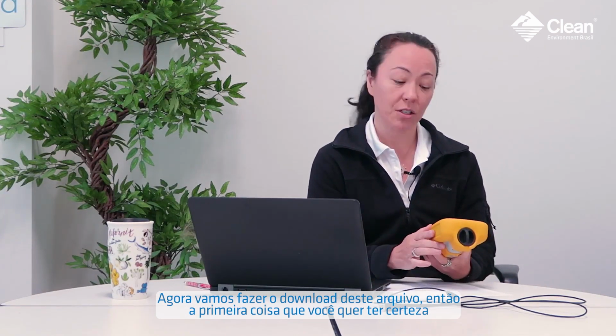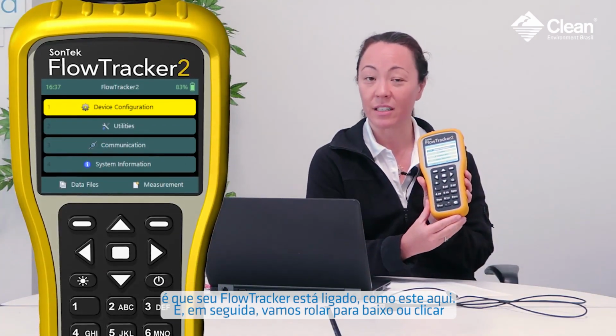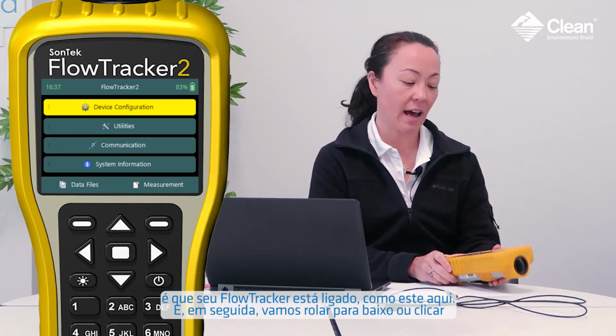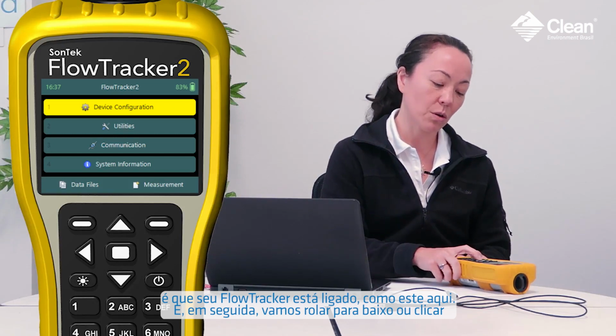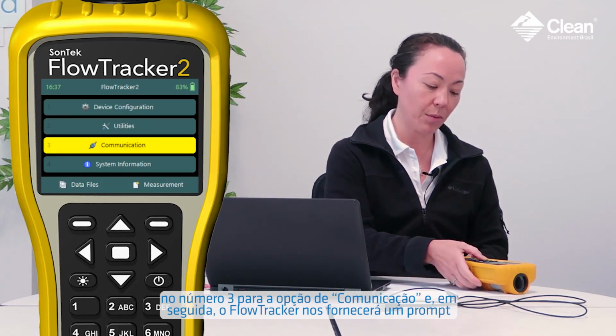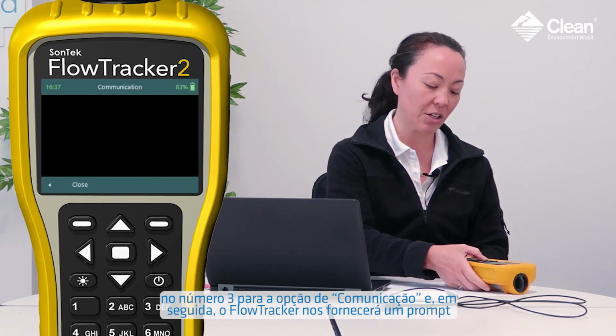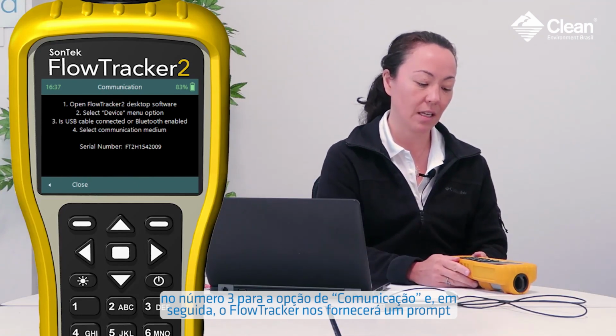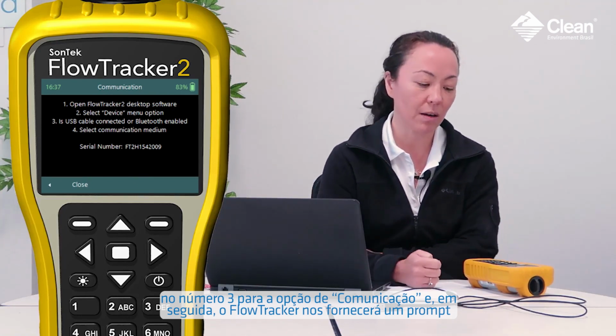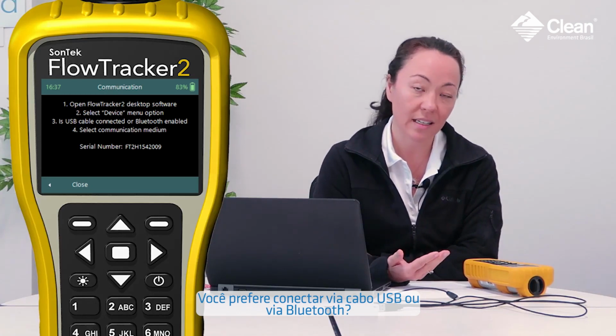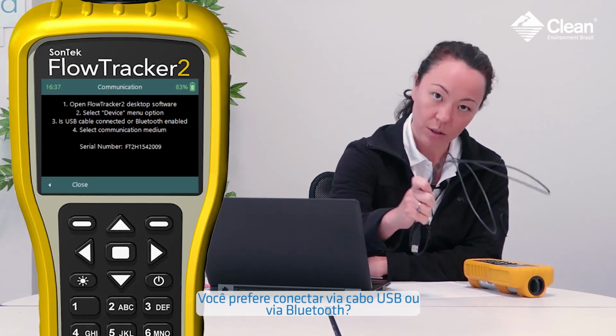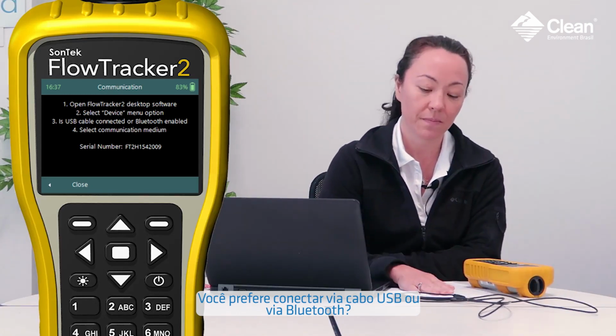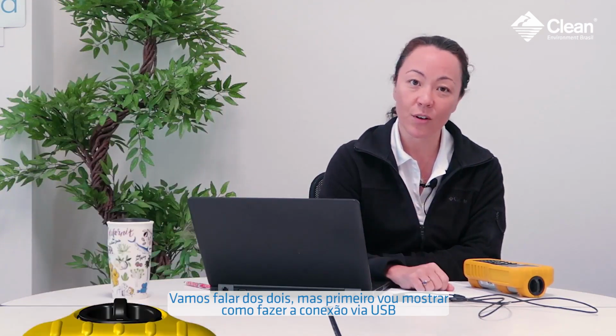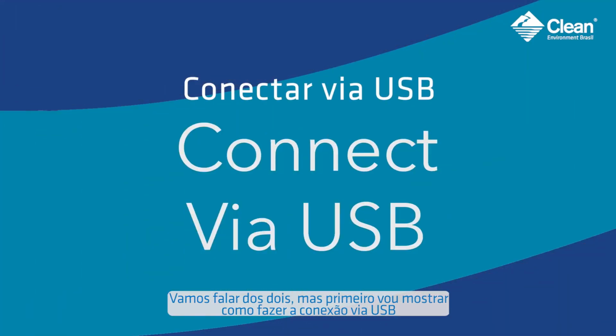So the first thing you want to make sure is that your FlowTracker is turned on, which I have. And then we're going to scroll down or click number 3 for the communication option. And then the FlowTracker gives us a prompt. Do you want to connect via the USB cable or do you want to connect via Bluetooth? We'll go over both, but first I'll show you how to do the USB connection.